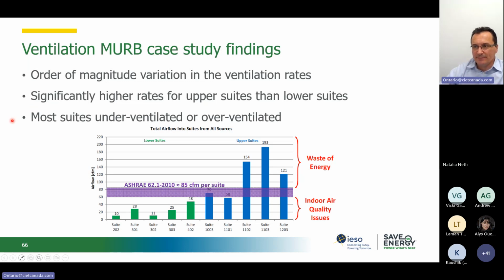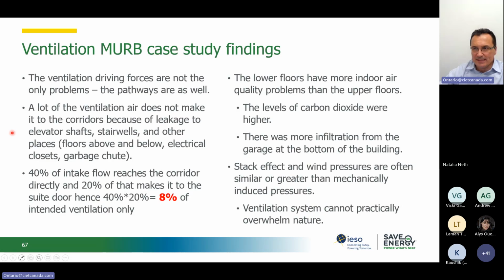So we had most buildings either under ventilated or over ventilated. So it was an opportunity for this project to correct the problem. And that's where the stack effect basically impacts the building air distribution. So findings here, we looked at the problem with air coming from the space, so the pressurization of the corridor wasn't operating properly.